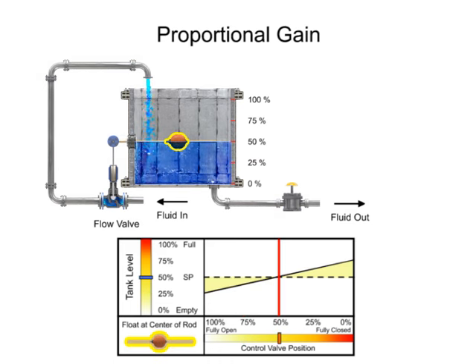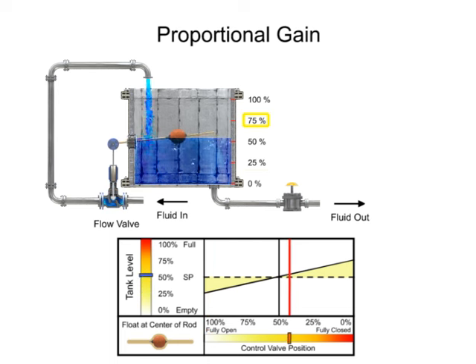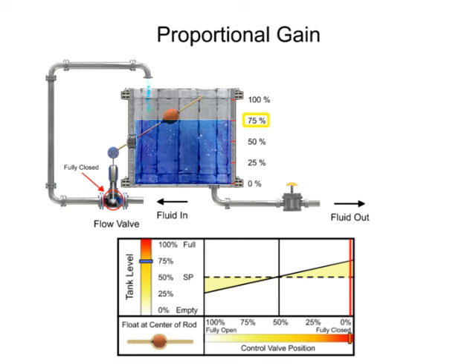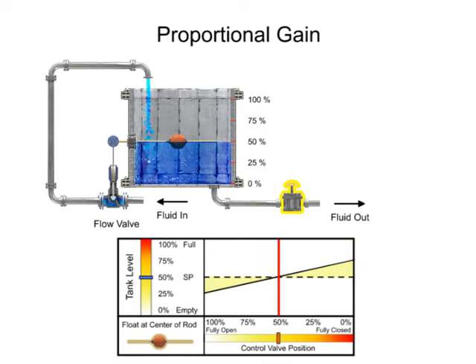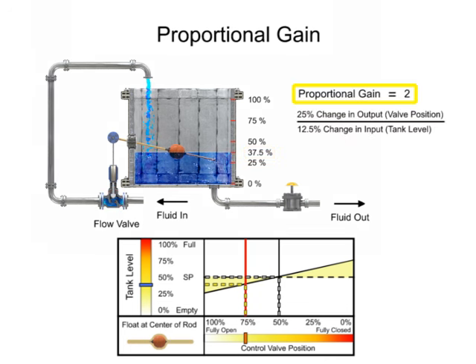Positioning the float to the midpoint of the bar increases the gain. The valve fully opens when the level drops to 25% and fully closes when the level rises to 75%. Opening the drain valve increases the load demand, which causes the tank level to drop by 12.5% to 37.5% full. The float drops and the valve opens 25%. A gain of 2 is demonstrated since the 12.5% change of tank level resulted in a 25% change of valve position.